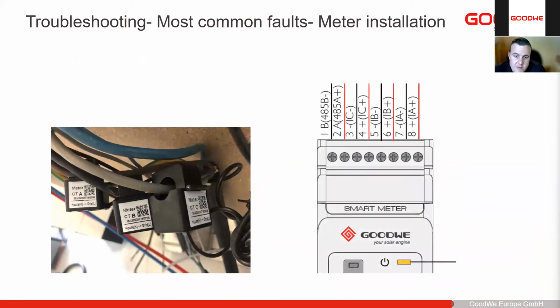The next point is very important. Very often our smart meter is not going to be installed in the customer's main distribution board because it's already full. So we have to install a subboard. We put the smart meter next door. We can run the CTs through trunking or cable trays. We undo that on the top of the smart meter, we route our cables nicely and we wire it back.